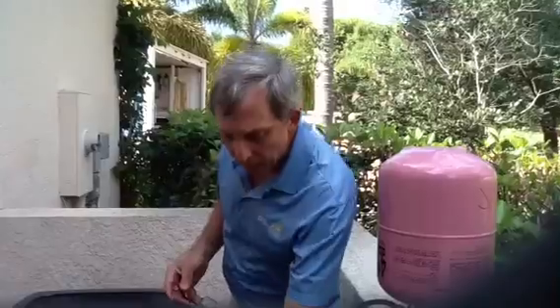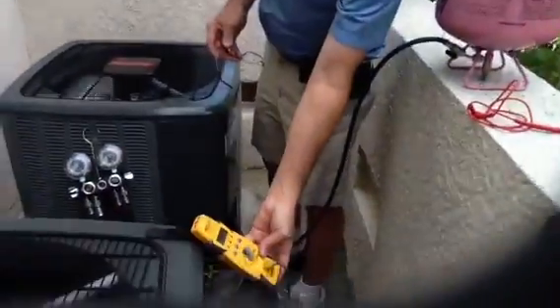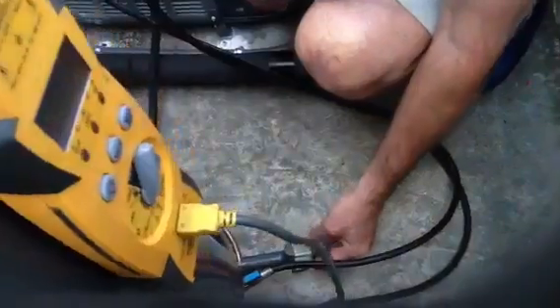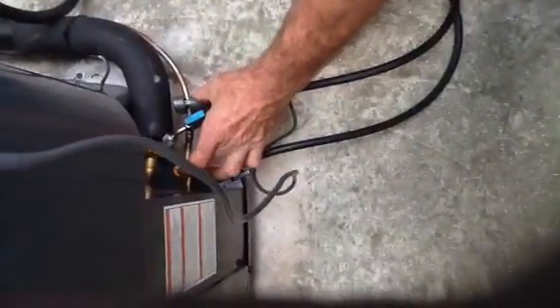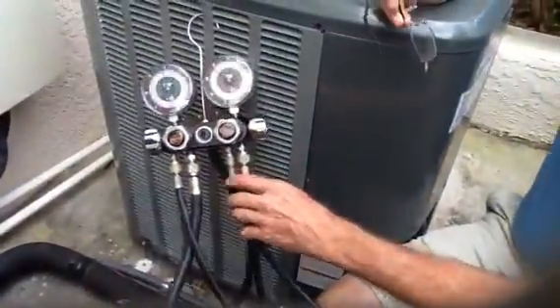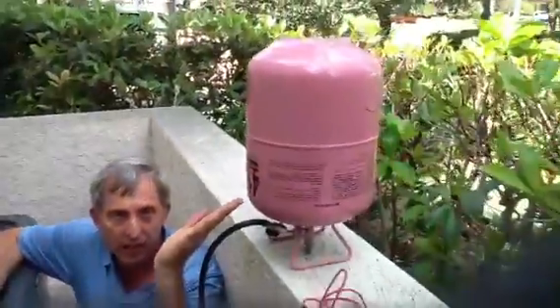I'm going to show you what you need to actually do a sub-cool. You've got to have a Fieldpiece meter, and you've got to have a temperature probe. Here's the temperature probe — it needs to be four to six inches from your liquid-line valve. You've also got to have a set of gauges, and you've got to have the R410A refrigerant.